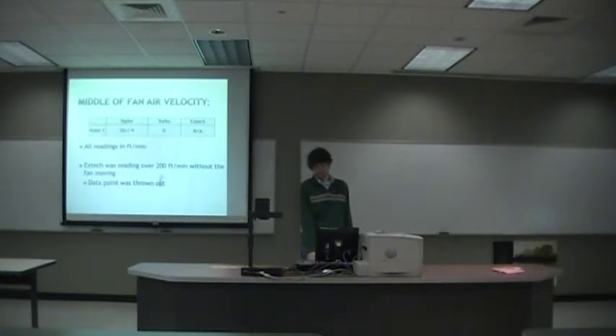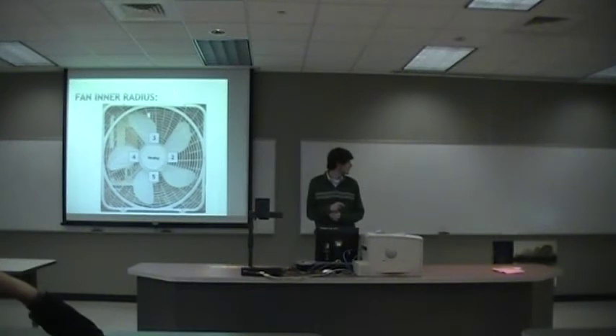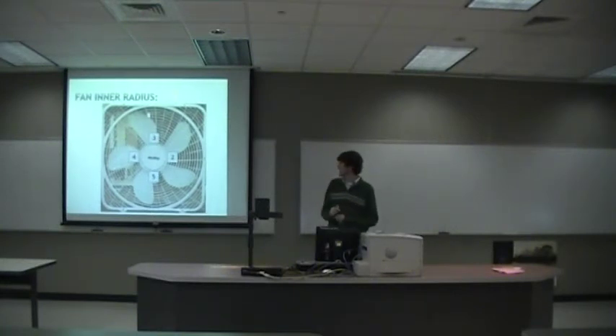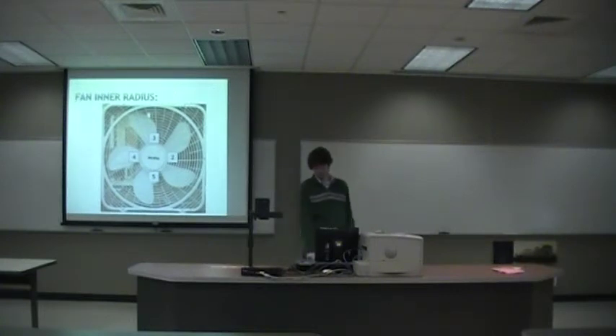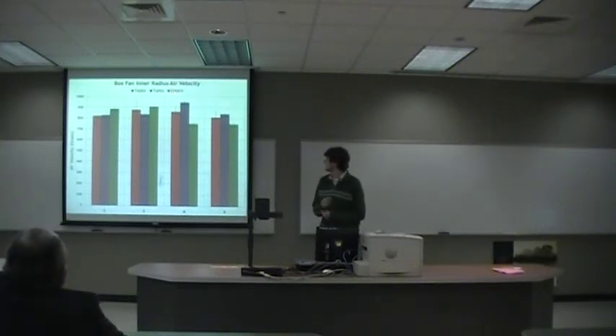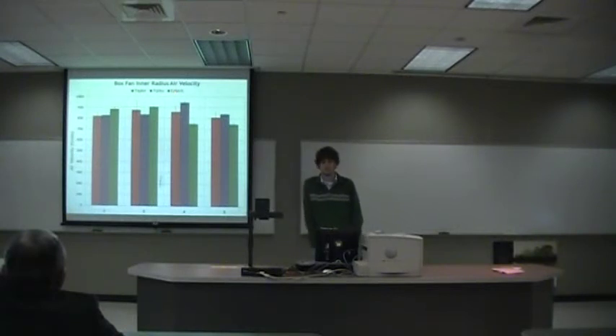After determining the air velocity in the middle of the fan, we looked at the inner radius of the fan. We took readings at four different spots around the inner radius, labeled 2, 3, 4, and 5. As expected, the velocity at each point was about the same since they were all the same distance from the middle — they were all in the 800 feet per minute range on all the devices.